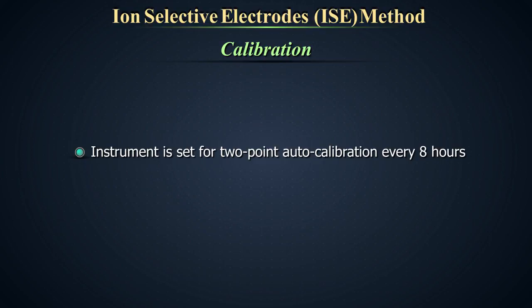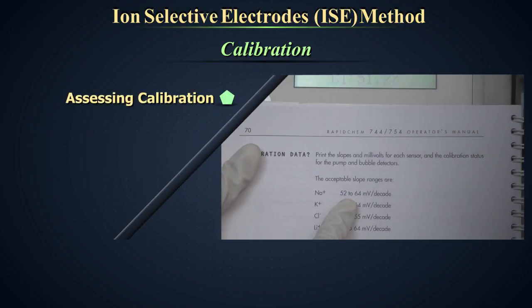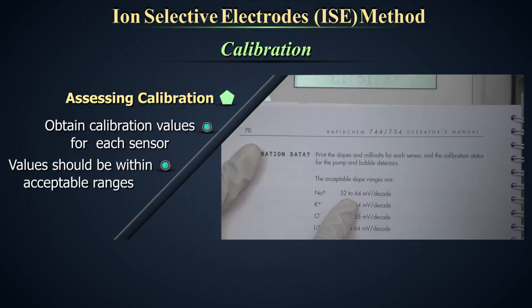Calibration. This instrument is set for 2-point auto-calibration every 8 hours by the manufacturer. It may differ for machines from different manufacturers. Assessing calibration. The calibration performed by the machine is assessed by obtaining calibration values for each sensor. These values should be within acceptable ranges which are defined by the manufacturer. Check these values daily and document.